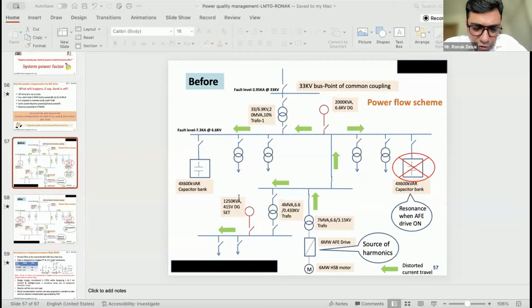The client faced lots of issues during the testing of this drive. I will also present the summary of the measurement. A very comprehensive power quality study was carried out with different operation scenarios, because this is the testing facility for high-speed rotors for turbines and generators. You cannot straight away achieve the speed of 3000 or 3600 rpm; you have to go gradually. So you have to fix certain operating scenarios during the harmonics measurement. With the drive on, and the 600 kVAr capacitor bank on and off, the resonance study was also carried out.